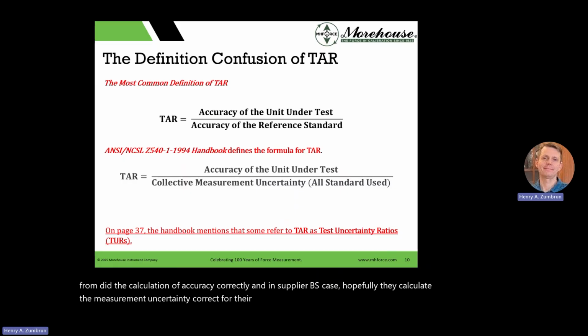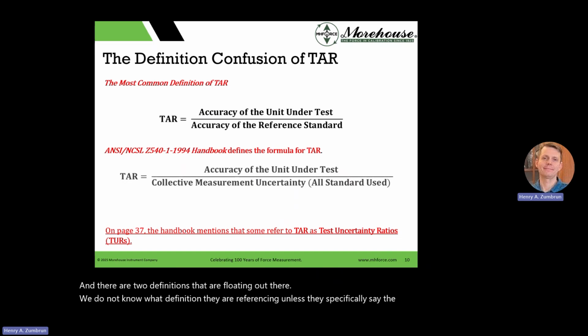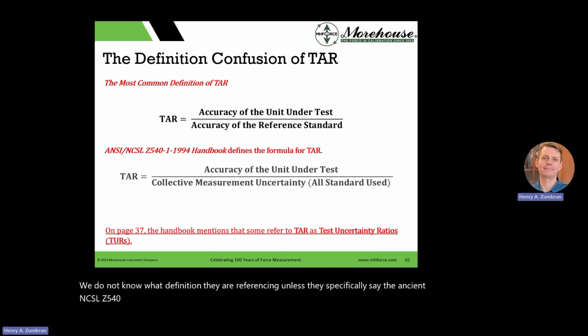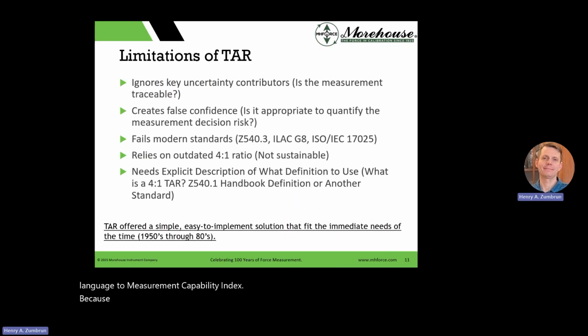But it's very distinct that when someone says TAR, and there are two definitions floating out there, we do not know what definition they are referencing unless they specifically say the ANSI NCSL Z540.1 1994 handbook. I know this is semantic, but this happens with TUR all the time, and it's another reason why JCGM 106 specifically recommends switching the language to measurement capability index, because there aren't two known, very distinct definitions for measurement capability index.